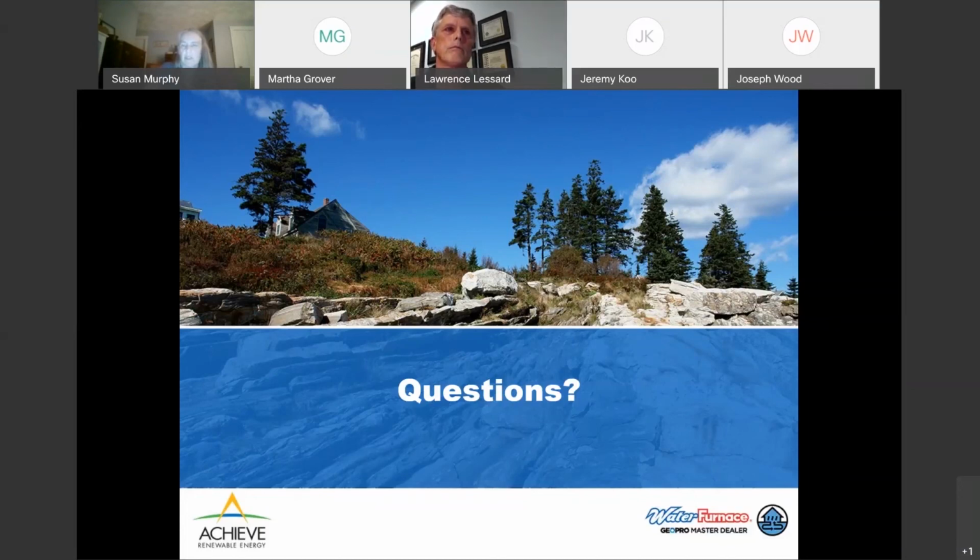And another question that I'm just going to ask, because I get it all the time, is the specific things about Melrose that might affect ground source heat pump, in particular, how ledgy it is here, and is that an issue for drilling for ground source heat pumps? Yeah, that's a common question, and the answer is somewhat counterintuitive. We prefer shallow bedrock. The drilling rigs are designed to drill through bedrock, and they move through bedrock quicker and less expensively than they do through soil.